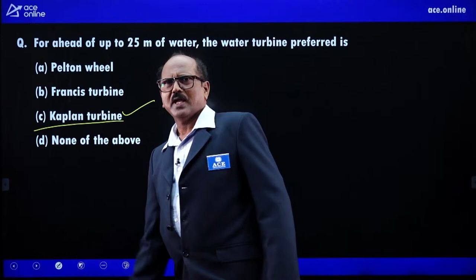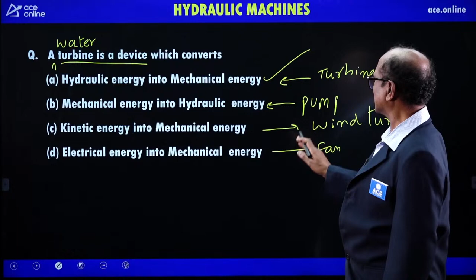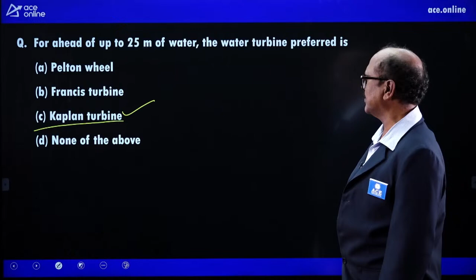25 meters up to, definitely Kaplan turbine. Head is less than 30 meters, Kaplan turbine. Previous is cleared, this one. Pelton is more than 250 meters. Francis is 30 to 250 meters.